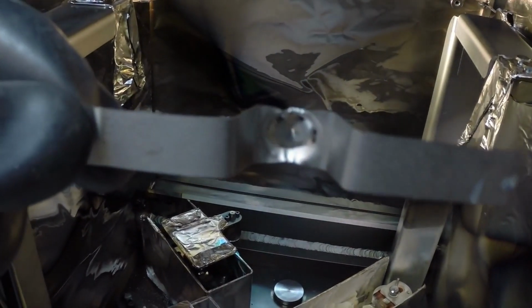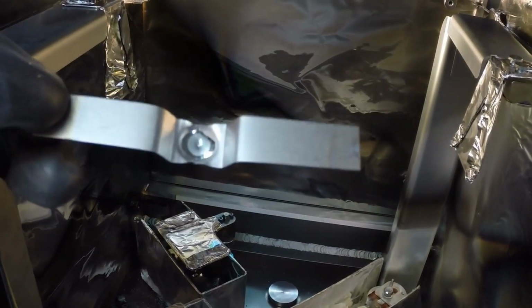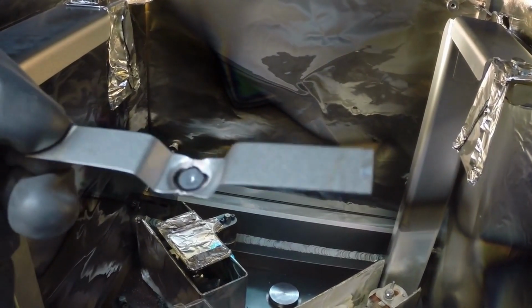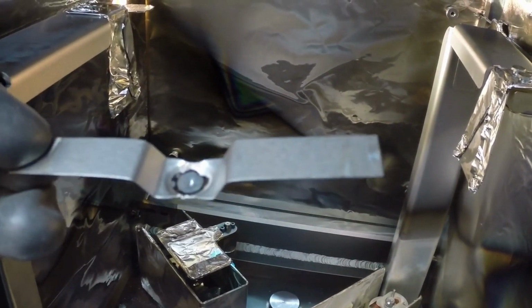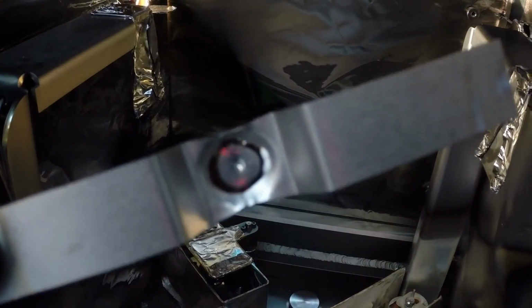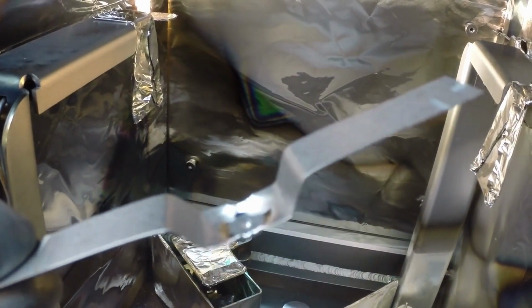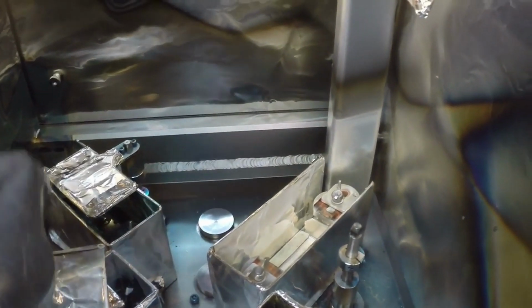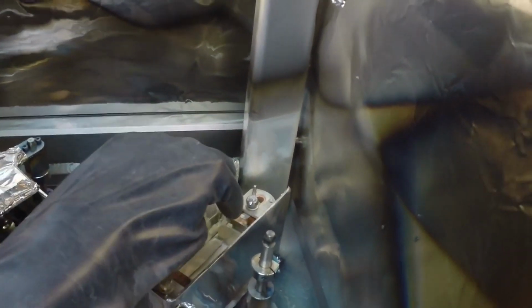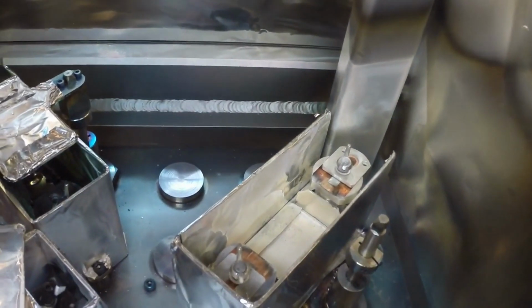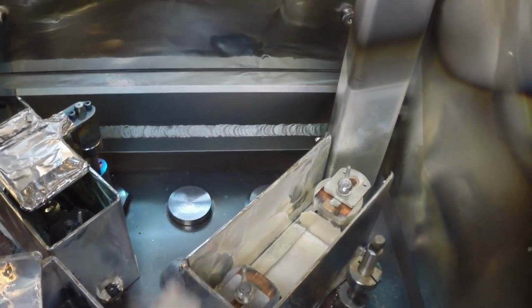In this case, we will use a tungsten boat because of the high melting point, low vapor pressure at elevated temperatures, high tensile strength, and low coefficient of thermal expansion of tungsten. You can also see there is already a bit of silver left over from previous evaporations. To install the boat, remove the source shield and loosen the boat clips. Place the boat in the middle of the source and then tighten the clips by hand.